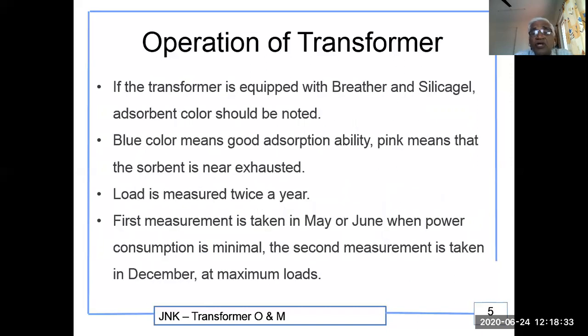If the transformer is equipped with a breather and silica sorbent, the color should be noted. Blue color means a good absorption ability. Pink means that the sorbent is nearly exhausted. Load is measured twice a year. The first measurement is taken in May or June when the power consumption is minimal. The second measurement is taken in December at the maximum loads, or as it may differ from your place also. You can change it, no problem on this particular one.